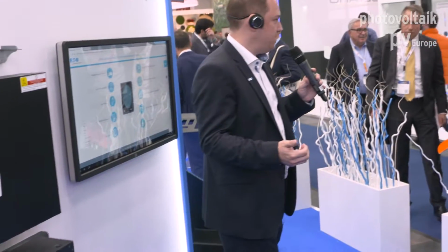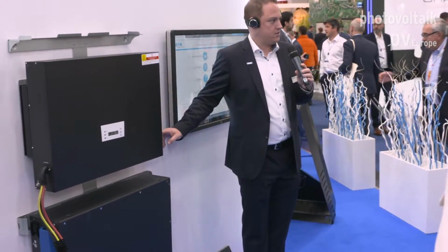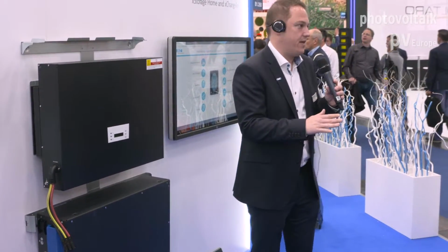On the lower connector blocks you have two connections. The first connection is, of course, the household. The second connector block is backup load. So one big feature, in case of a grid outage, the system can switch over in less than 50 milliseconds, around about 20 milliseconds, to the critical loads. Critical loads could be like heating, refrigerators, lights. You want to stay on even if the grid is not there anymore.